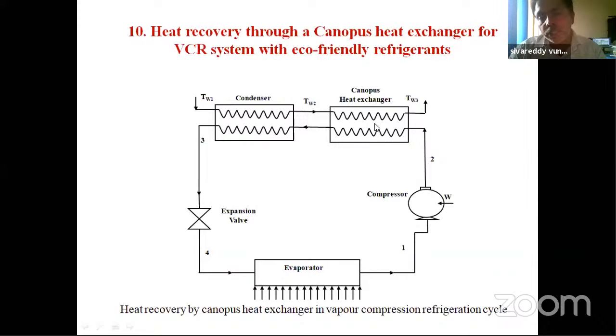At the condenser, generally the condenser temperature is 40 to 45 degrees, where phase change takes place from vapor to liquid. But after compression, it reaches a superheated condition, not critical. If the condenser temperature is 45 degrees, the compressor exit vapor temperature can be more than 70 or 80 degrees—at least a 30 to 40 degree difference. You are capable of extracting that sensible heat, but the latent heat has no use since ambient is also around 40, so that 5 degree difference is not useful.